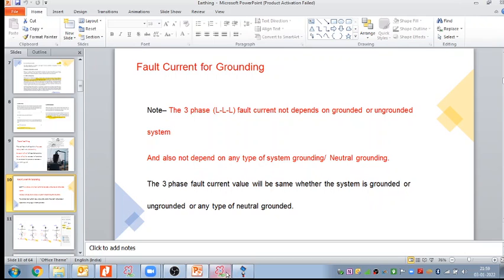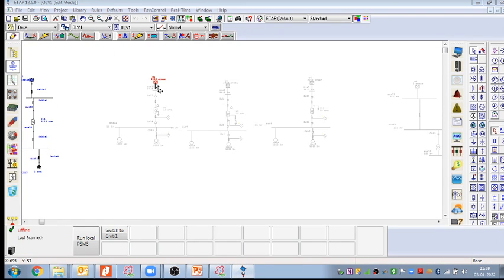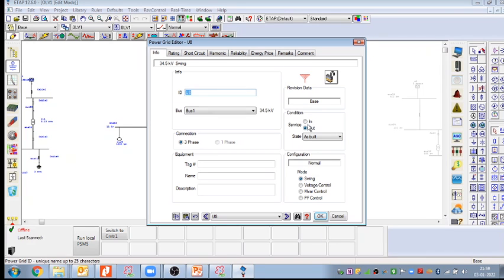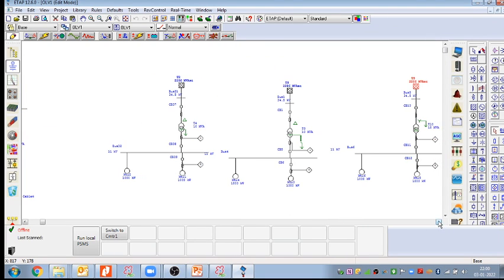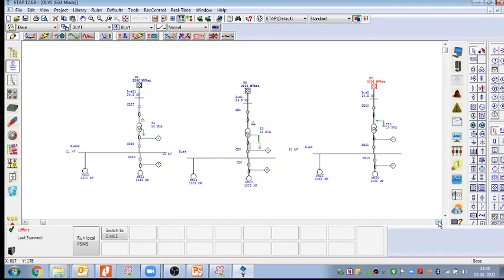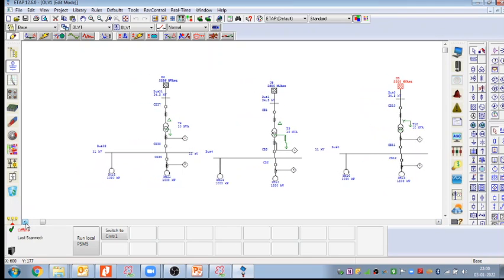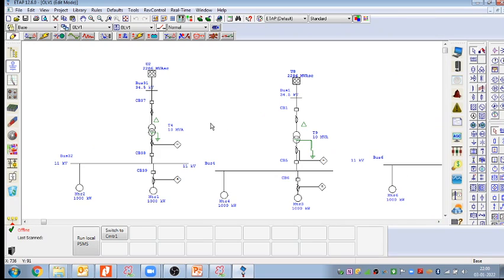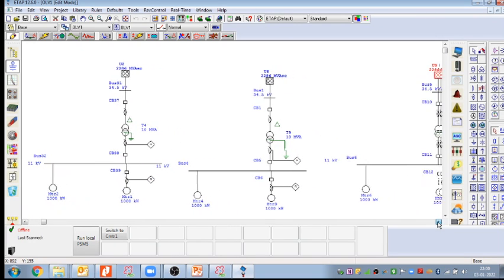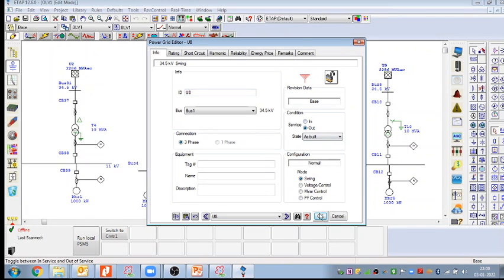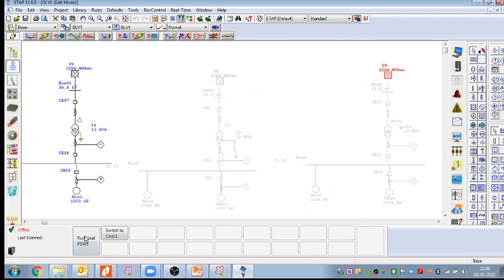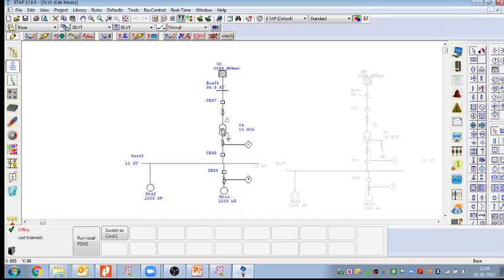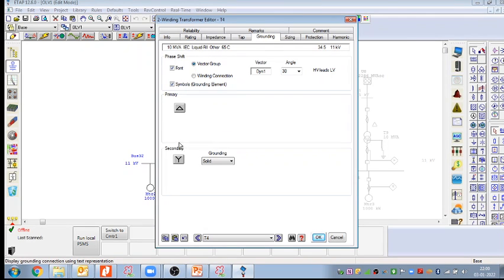We can understand this by an example. Let me take an example here; we have developed some cases. First of all, let me take this service out, and this case also service out. Let me take one case like this and convert this transformer to primary delta, secondary star winding, and the grounding is solid grounding. Let me take the open grounding, which means the grounding is open, meaning an ungrounded system. Click on OK.